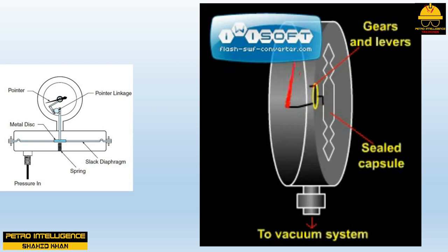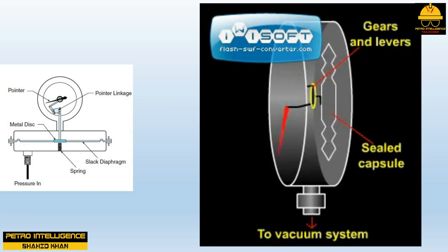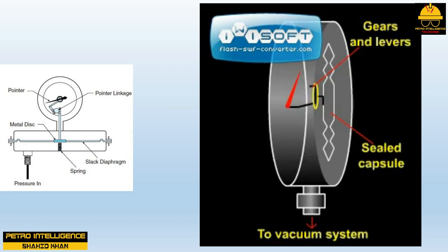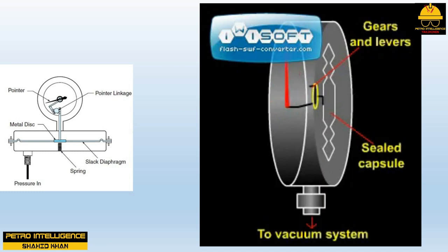The third type of pressure element is a diaphragm, which comes in two basic types: diaphragm capsule and slack diaphragm. The metallic diaphragm capsule consists of a metal cup covered by a flexible metal plate, a pressure inlet, mechanical linkage, and pointer; it is designed to measure small pressure changes, with dome flexing transferred proportionally to the pointer. The slack diaphragm pressure element consists of a flexible diaphragm attached to a spring, pressure inlet, mechanical linkage, and pointer; it is designed to operate under very low pressures of 0 to 0.5 PSI.